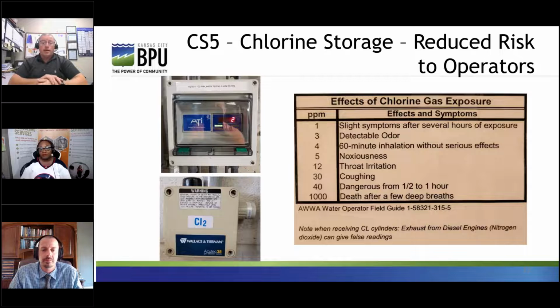And the final case study, chlorine storage reduced risk to operators. The plant was built with an in-building but isolated chlorine storage room. It's protected from accidental release of chlorine by a gas scrubber system. It has 3 chlorine sensors that when activated turn on the scrubber to ventilate the room.